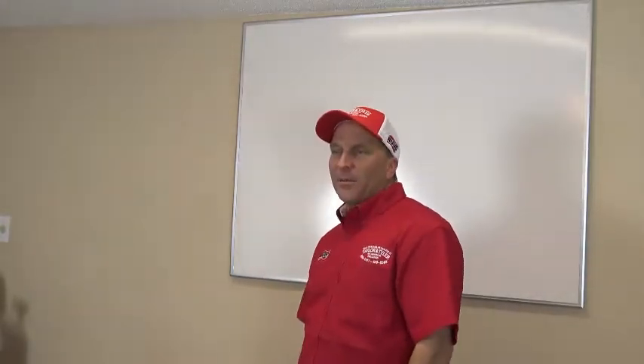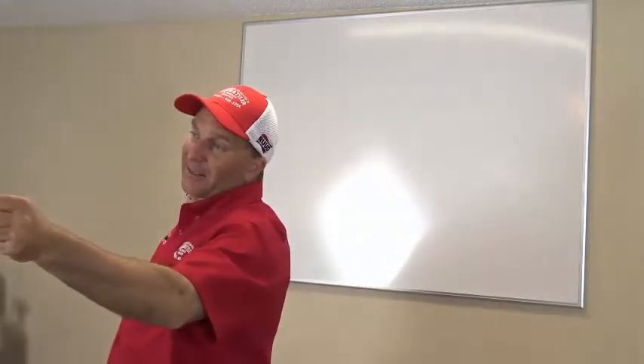Well, hey, I got a time delay on my thermostat, so that's going to prevent that. No, it won't. You know why? Because you got a battery-operated thermostat, and the battery is continually holding together the R and the W, the R and the Y, and it's constantly sending voltage out to it. Okay, or it's constantly making that contact, so it's not seeing a short cycle.